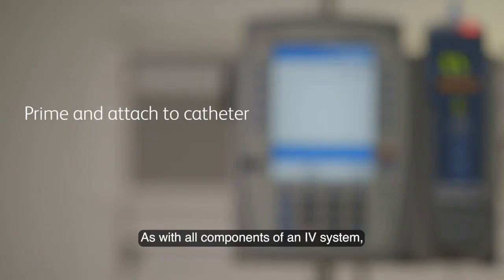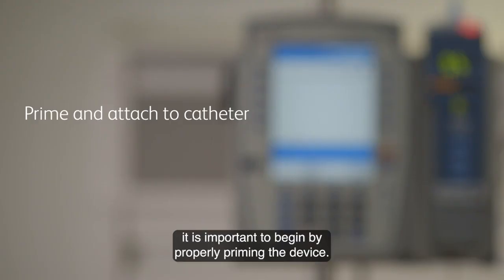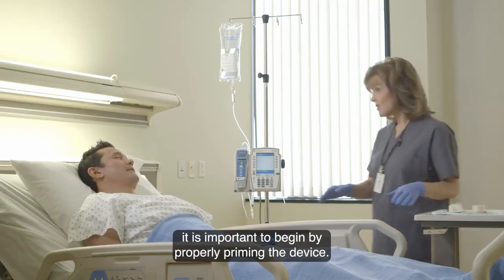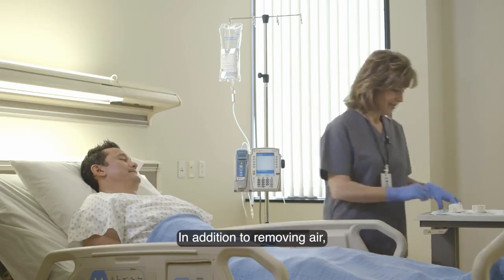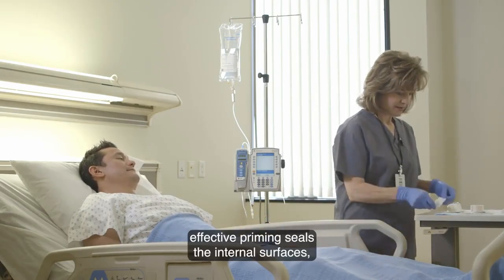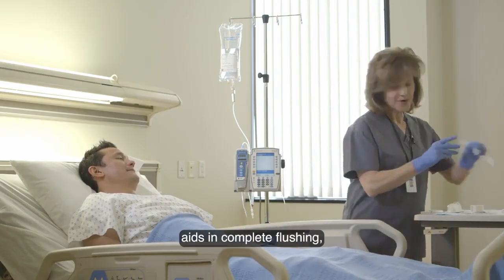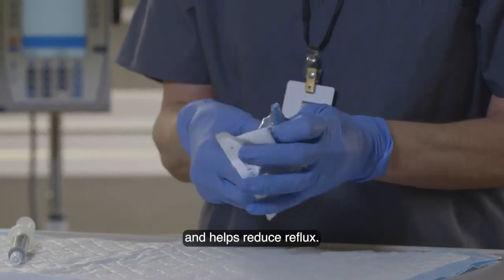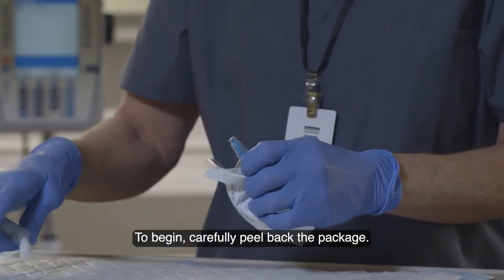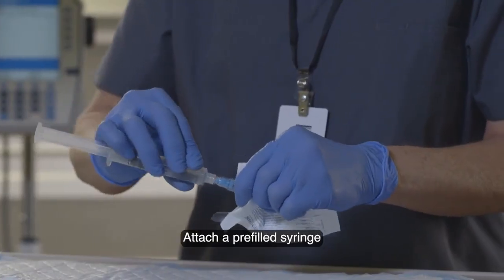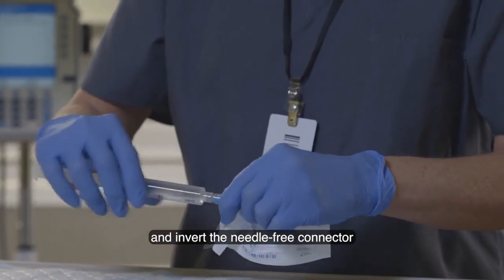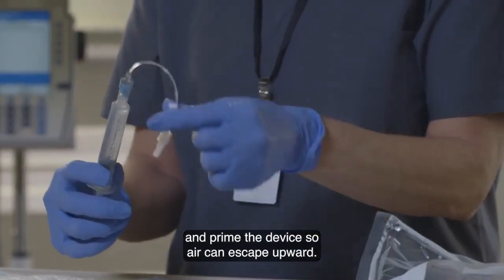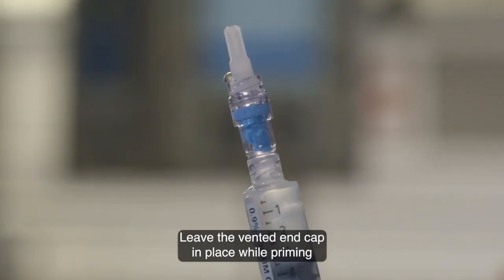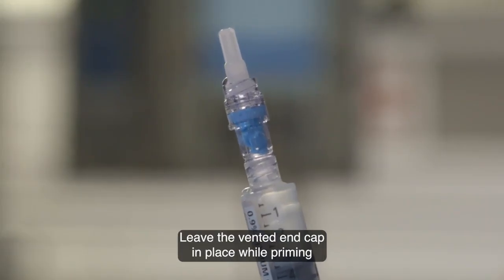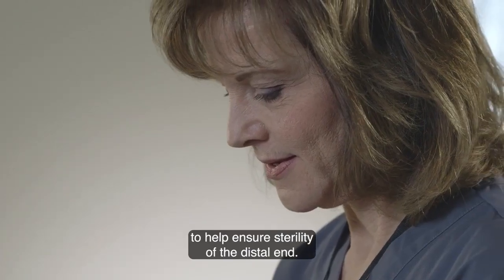As with all components of an IV system, it is important to begin by properly priming the device. In addition to removing air, effective priming seals the internal surfaces, aids in complete flushing, and helps reduce reflux. To begin, carefully peel back the package, attach a pre-filled syringe, invert the needle-free connector and prime the device so air can escape upward. Leave the vented end cap in place while priming to help ensure sterility of the distal end.